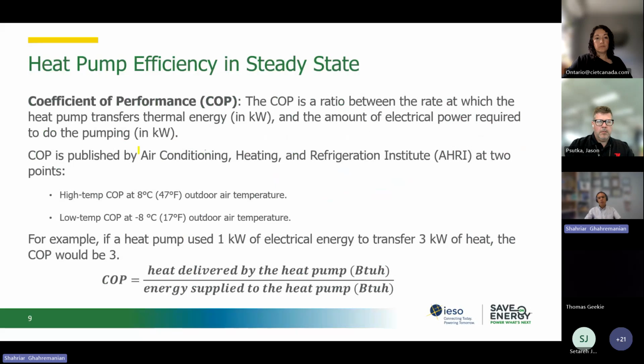First, I have two steady state efficiency terms. One of them is the coefficient of performance, which is basically the amount of heat delivered by the heat pump. It depends on the season we are talking about. If it's the heating season, it means how much heat was brought to the building, and in the cooling season, it is how much heat we extracted from the building, divided by the amount of electricity provided to the heat pump. This can be in units of BTU per hour, kilowatt hour, or any other units that we want. So this is the COP.